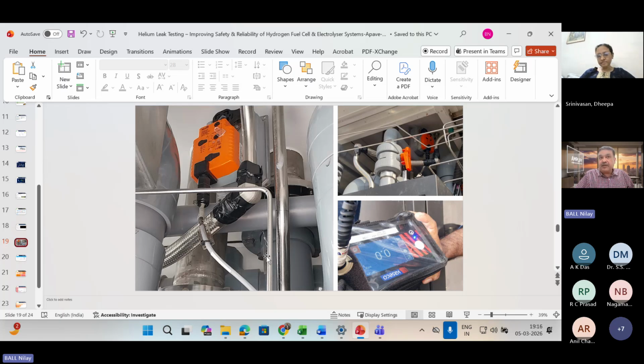The challenge is that these are all carbon steel piping where you're using gas, which can be easily detected by a bubble test. When the gas is passing through the joints, you can use a soap solution to detect bubbles. But hydrogen will not form a normal bubble with soap solution, you cannot detect hydrogen that way. You need special bubble-creating solutions to detect hydrogen cracks in large diameter pipelines, but they are very expensive.